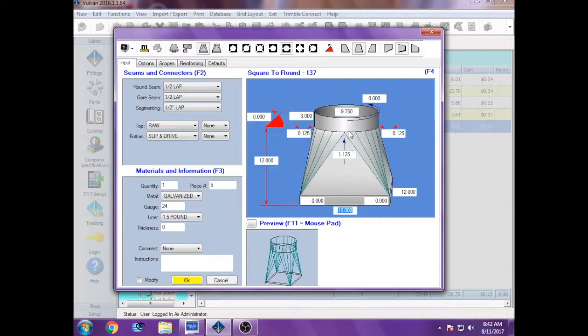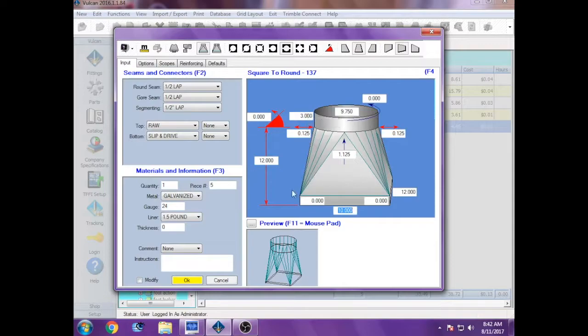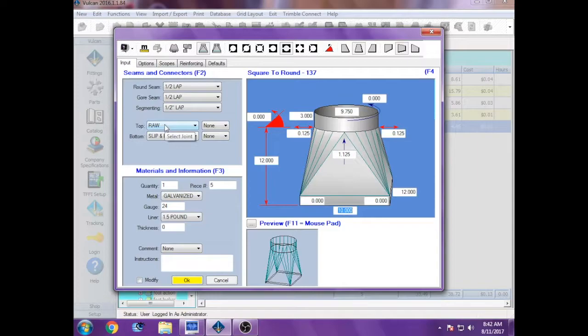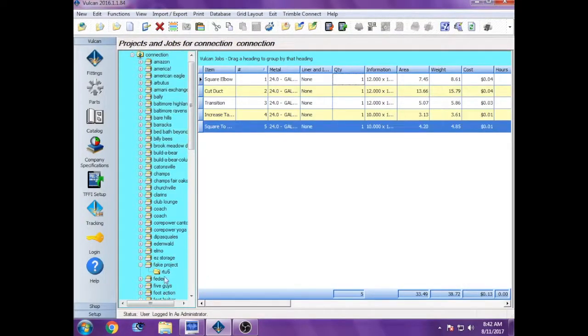You can use these boxes here to offset it as needed. The collar pretty much is always three inches. You always leave it as a half inch lap to make the connection. The bottom can be changed from slip and drive to flanges or whatever else they might need, but the top should always be raw. And the gauge is 24 to keep it on the same piece of metal.